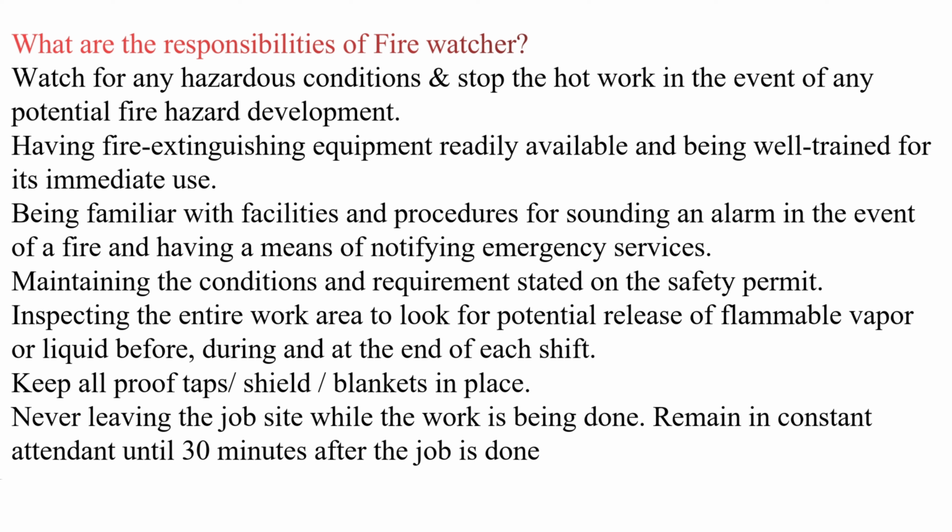What are the responsibilities of a fire watcher? Watch for any hazardous conditions. Stop the hot work in the event of any potential fire hazard development. Having fire extinguishing equipment readily available and being well trained for its immediate use. Being familiar with facilities and procedures for sounding an alarm in the event of a fire and having a means of notifying emergency services.